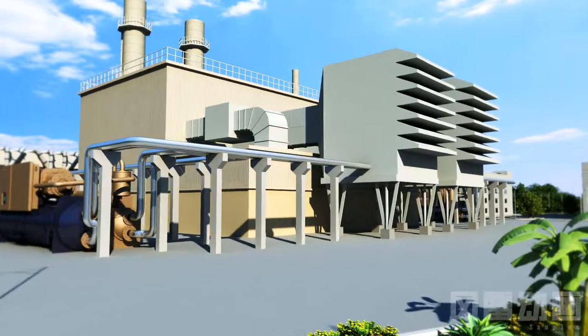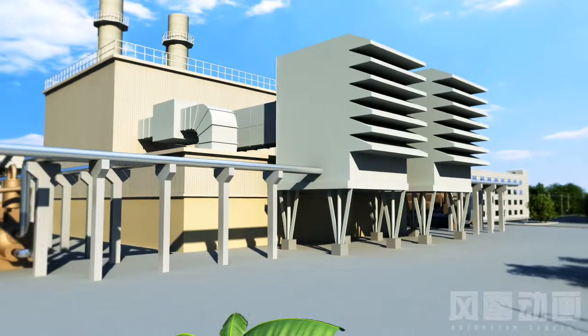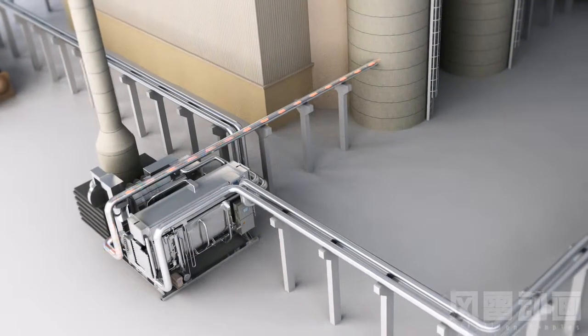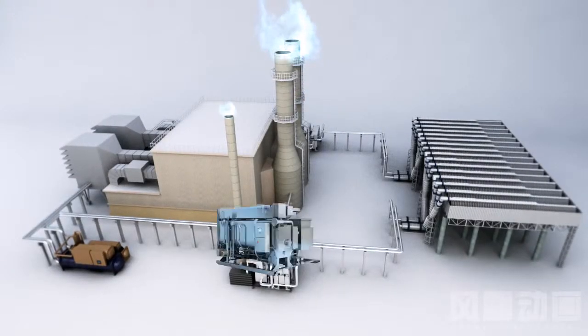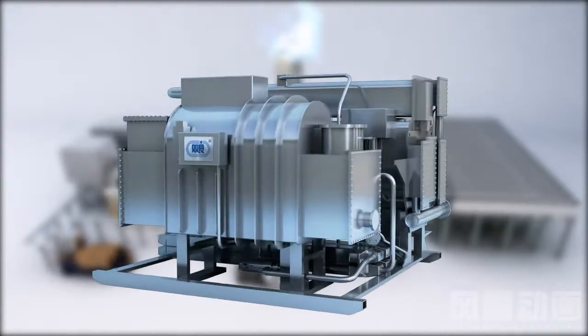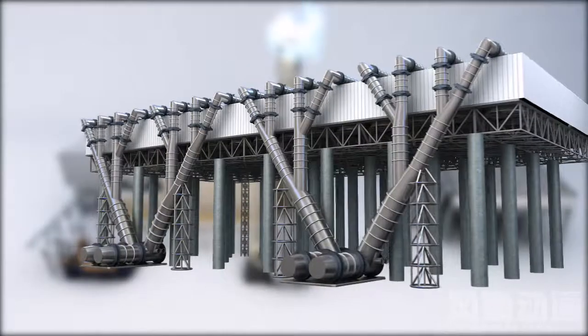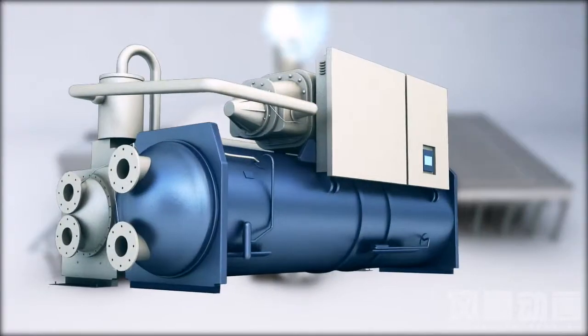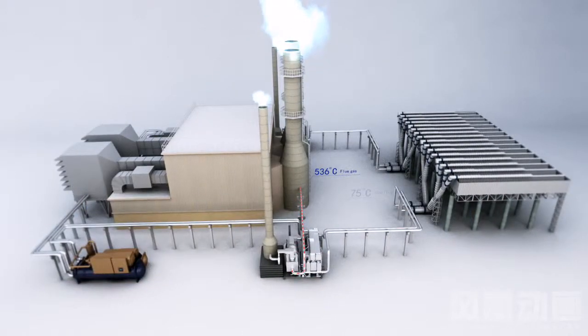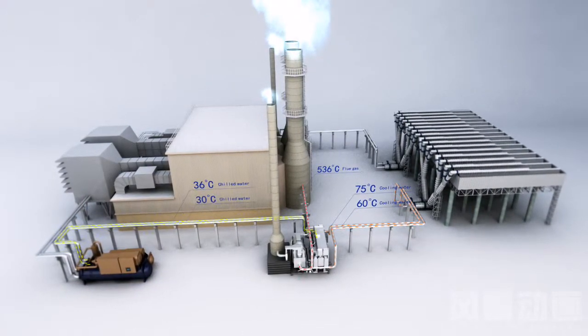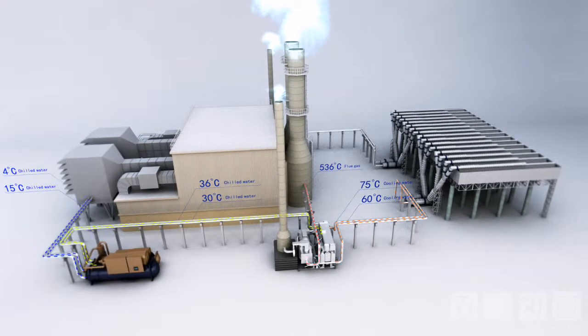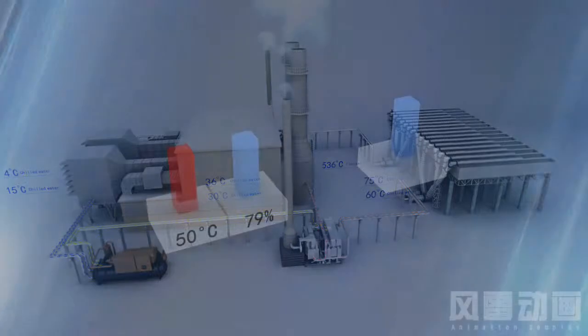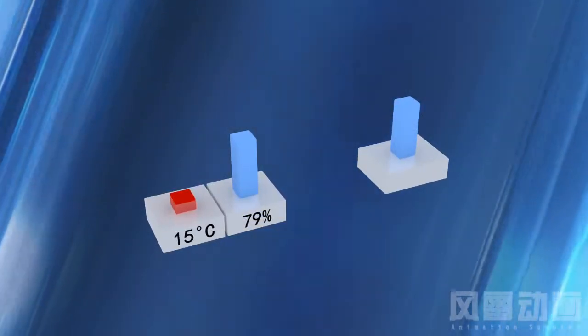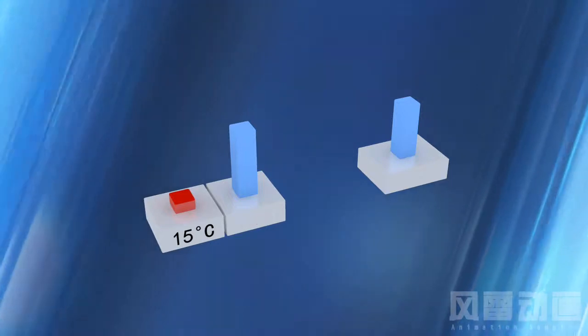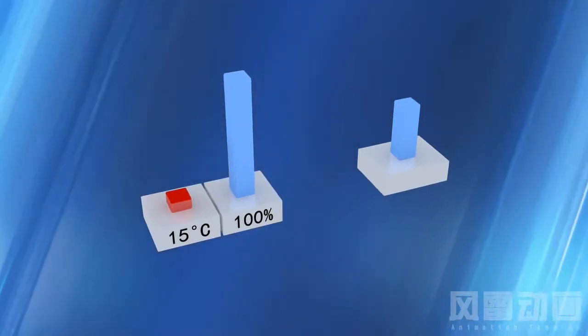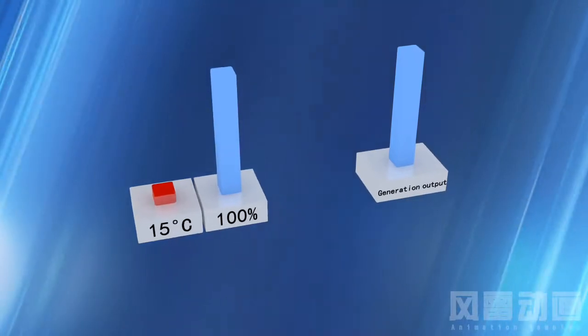The technology utilizes the waste heat of the high-temperature flue gas produced by the single-cycle gas turbine as power, taking the absorption chillers as the main equipment, the air coolers as the main cooling equipment, the electrical chillers as the auxiliary equipment, with a whole set of advanced Shuangliang technology as the support. To reduce the air inlet temperature to 15 degrees centigrade, thus 100% generation output can be achieved accordingly. The generation output can be enormously improved. Shuangliang air inlet cooling systems technology is the best solution for gas turbine inlet cooling systems.